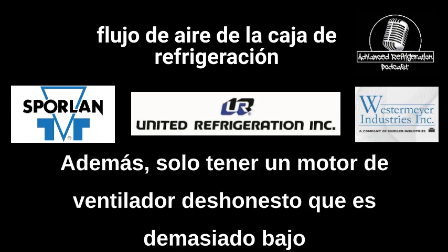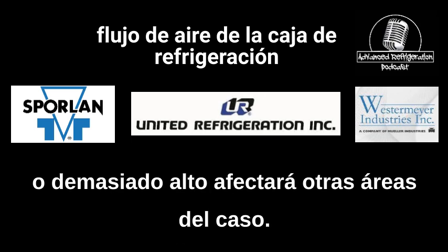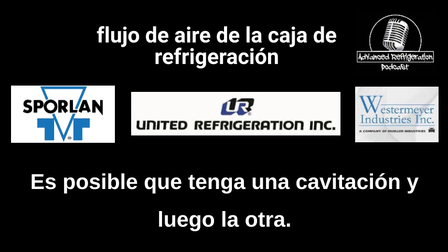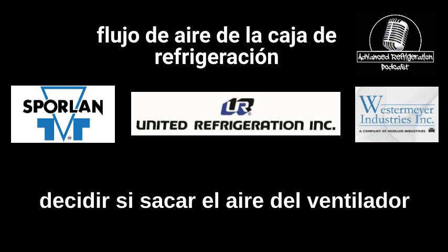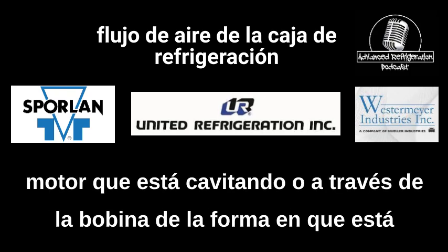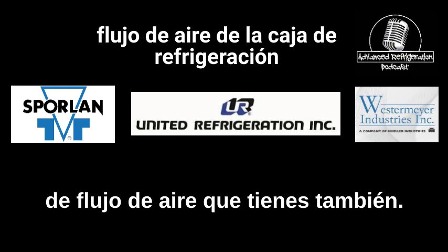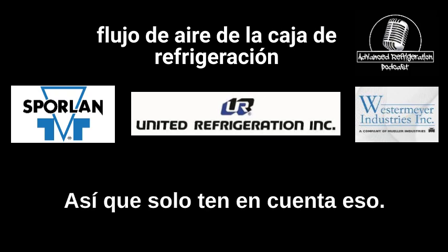Also, just having one rogue fan motor that's either too low or too high will affect other areas of the case. So just be mindful of that. You might have one cavitating, and then the other one's deciding whether to pull the air out of the fan motor that's cavitating or across the coil the way it's intended to, which is also going to reduce the amount of airflow that you have as well. So just be mindful of that.